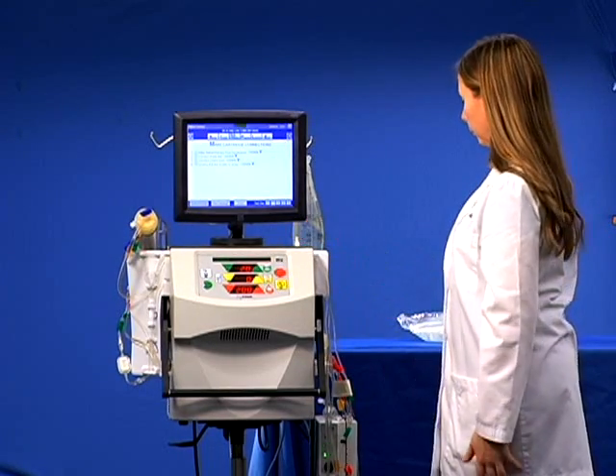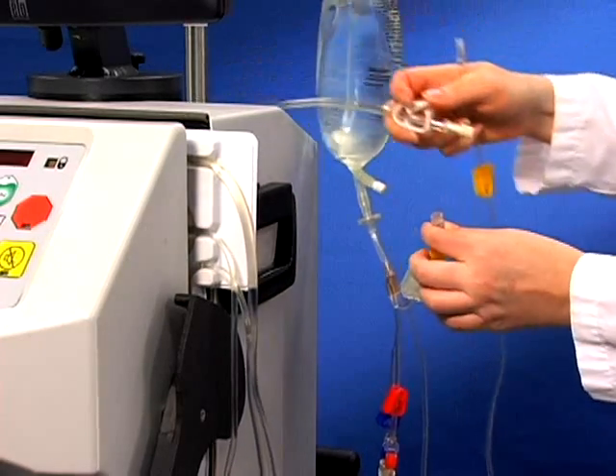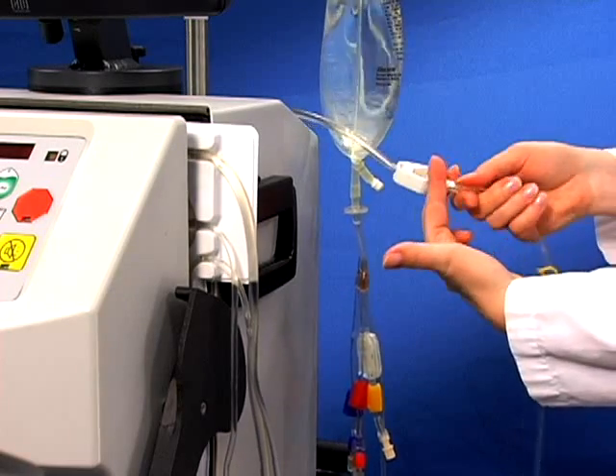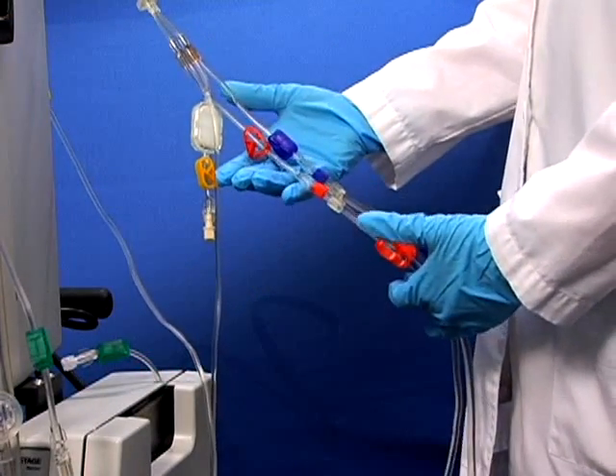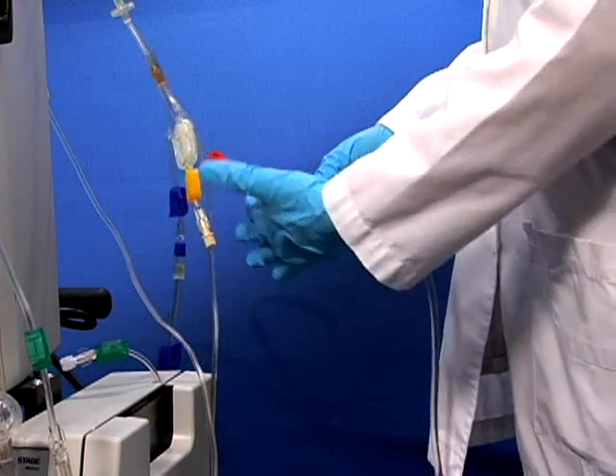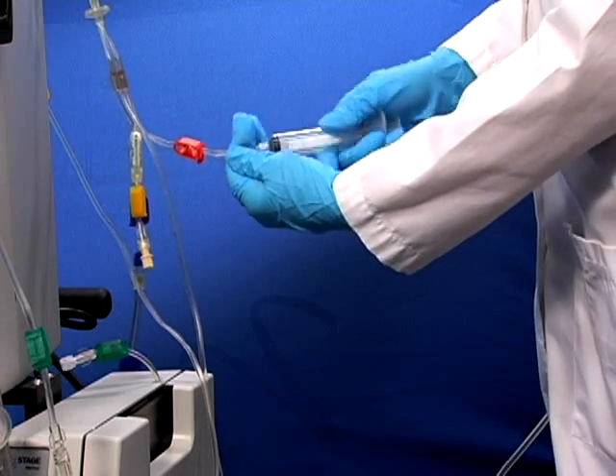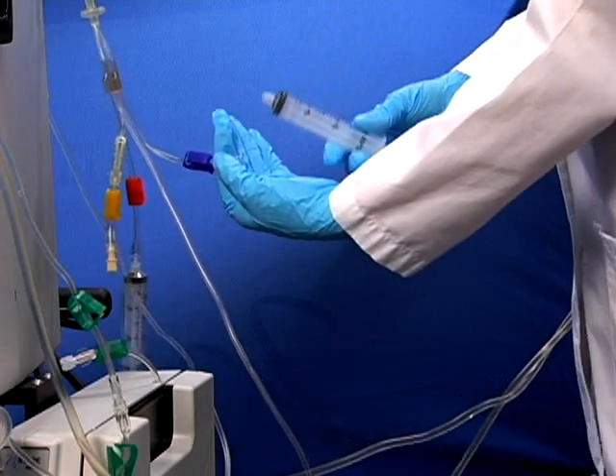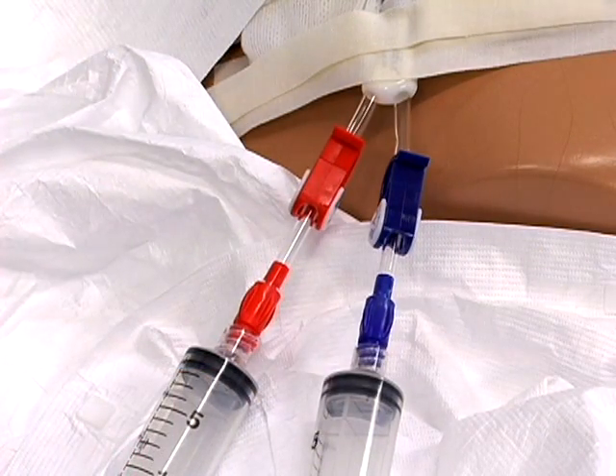Go back to the priming spike and find your yellow waste line. Clamp and disconnect this line and connect it to the waste line extension. Unclamp both. Locate the patient lines at the priming spike. Clamp and disconnect. Connect patient lines to the patient's vascular access and unclamp all clamps.